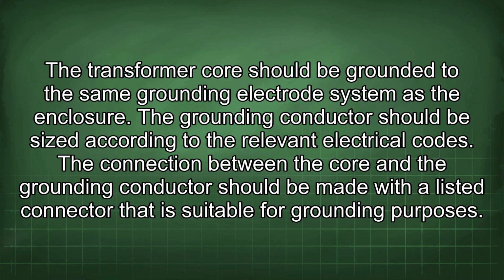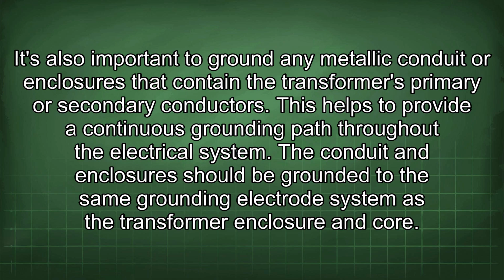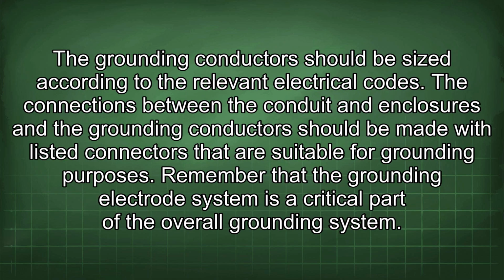It's also important to ground any metallic conduit or enclosures that contain the transformer's primary or secondary conductors. This helps to provide a continuous grounding path throughout the electrical system. The conduit and enclosures should be grounded to the same grounding electrode system as the transformer enclosure and core. The grounding conductor should be sized according to the relevant electrical codes. The connections between the conduit and enclosures and the grounding conductors should be made with listed connectors that are suitable for grounding purposes.